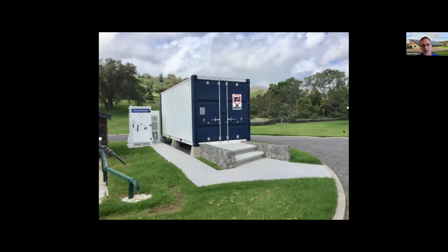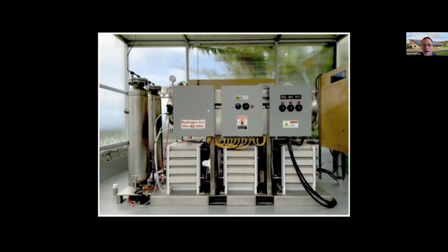We recently went online with a solar project that took way too long to get through the county and state, but it's operational now. It consists of about 350 kilowatts of PV and a 1 megawatt hour battery. The container is the 1 megawatt hour battery, with 480 Sony modules making up that 1 megawatt. It's actually redundant, two 500 kilowatt hour banks we can turn off individually, so when we do maintenance we can shut down half and keep it running.